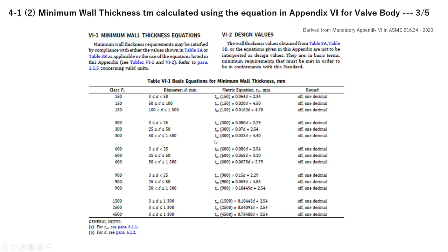Another equation can be used, the equation of Table 6-1. This is in mandatory Appendix 6. So this is Table 6-1. Translating class 300 and diameter D equal to 76.2 millimeter, this line: Tm equal 0.033 multiplied by D plus 4.40. Round off to 1 decimal. So this equation is to be used.